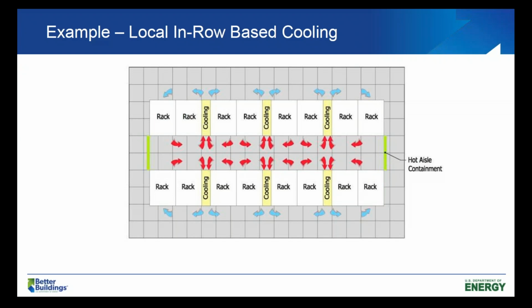So here's an in-row based cooling. This is now a plan view. This is an example of the APC in-row cooler, where these cooling modules are placed in the row next to the rack, and the hot aisle is contained. The hot air goes right through the cooling system, then back out, and the main data center space is basically cold, a cold aisle, if you will. You can do this with no raised floor. The airflow goes in a horizontal loop instead of a vertical one, if you will. So there's no above-ceiling plenum, and there's no below-floor plenum in this arrangement. Next slide.